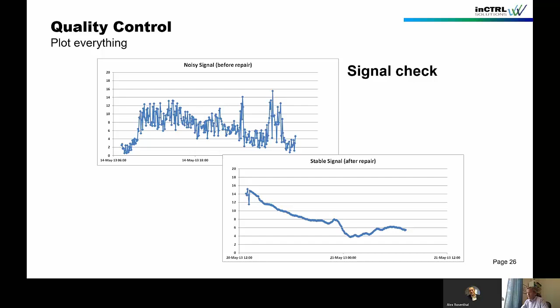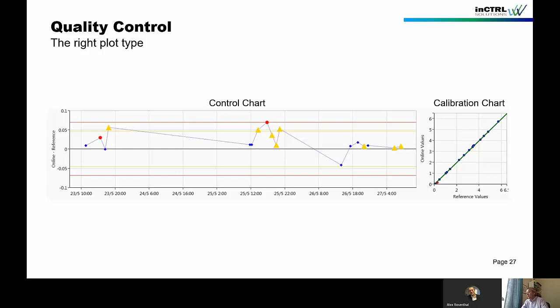Also find the right plot type. For our reference measurements, we plot that in a Shewhart control chart. What that is, we are plotting the difference between the sensor and the lab value over time. Very good to detect any drifts, outliers, shifts, jumps, whatever. However, what you don't get out of that chart is information on the measuring range. So if you have a wrong calibration, you would not easily be able to detect that. So that's why we have the calibration chart as well, and that gives us a very good indication of the calibration. Okay. So let's stick a little bit longer to that reference sampling.